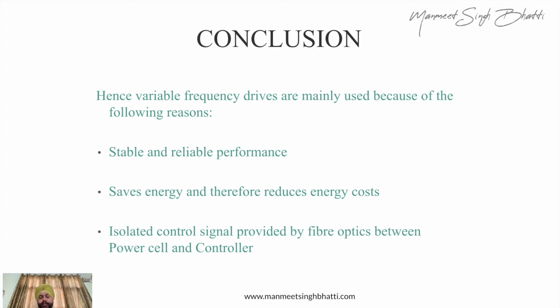Next benefit is that isolated control signals can be given to this. So for all the VFDs which you need to control, you can actually use fiber optics nowadays. So you can have your controllers kept anywhere in your plant, and power control in a different MCC, and you can actually control it. So these kinds of technologies are available nowadays with the VFD, and as per your need, you can actually design the complete system, and it is going to get you the savings.